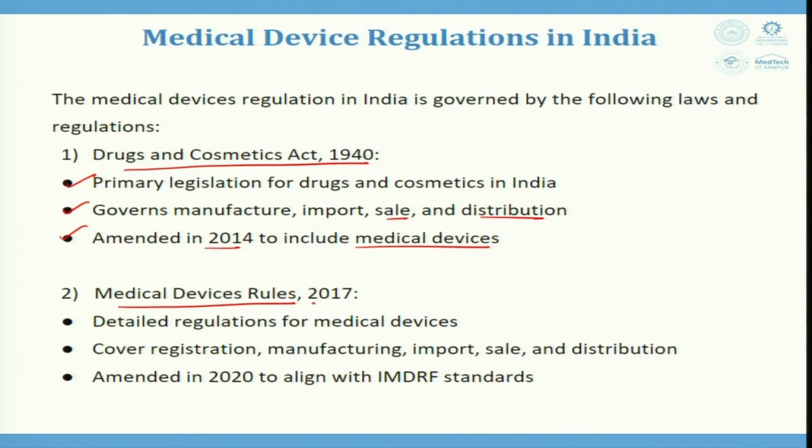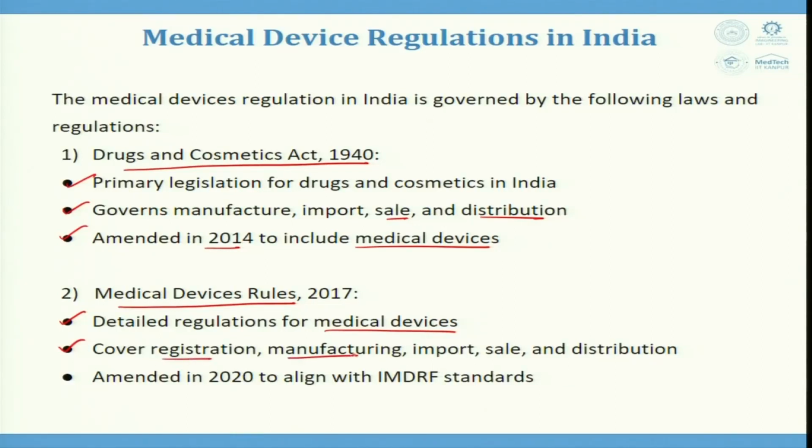Now, the Medical Devices Rules, that is MDR 2017, has a detailed regulation for medical devices. Whenever a medical device company or medical prototyping company such as MedTech facility at IIT Kanpur, we need to keep the files of the MDR 2017 to understand these are the rules that we are going to apply to maintain our ISO standards, that is the ISO 13485 standard that is being maintained here at IIT Kanpur. So, this covers the registration, manufacturing, import, sale and distribution of the medical devices that we are trying to prototype here. This was also amended in 2020 to align with IMDRF standards.